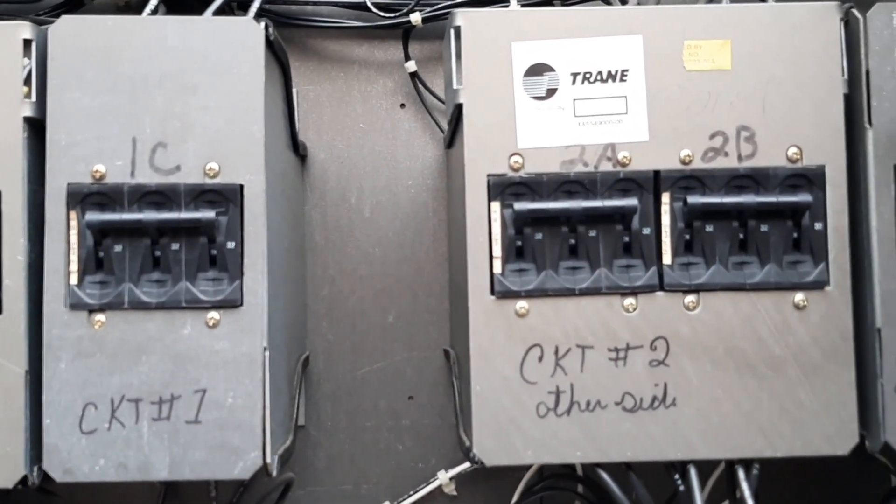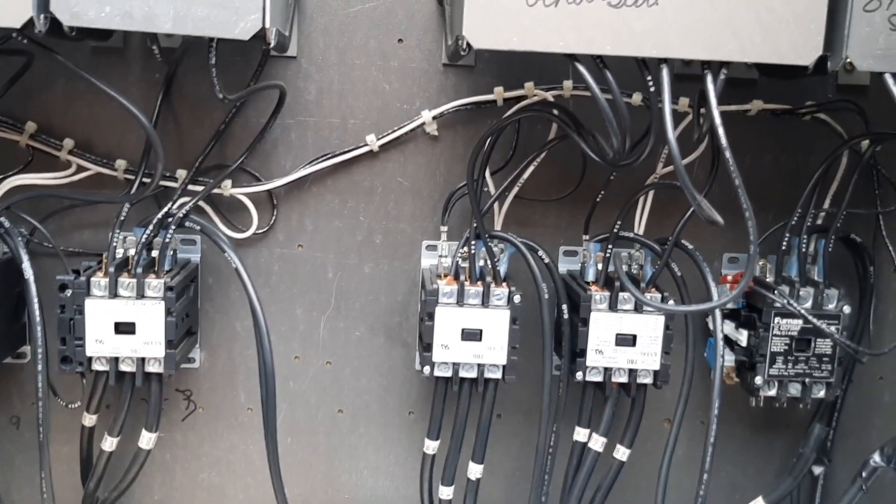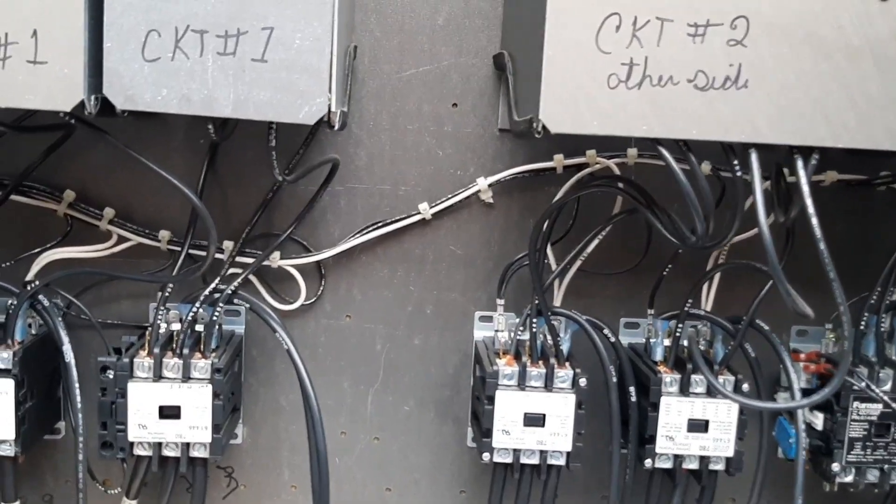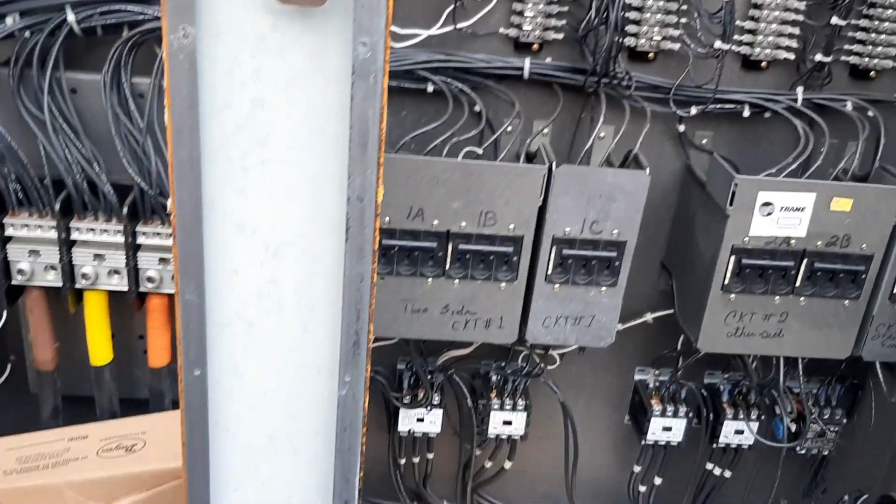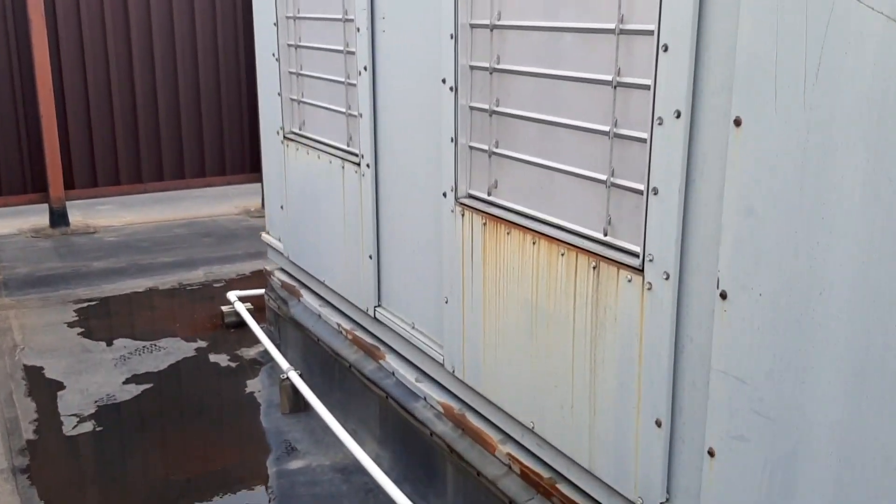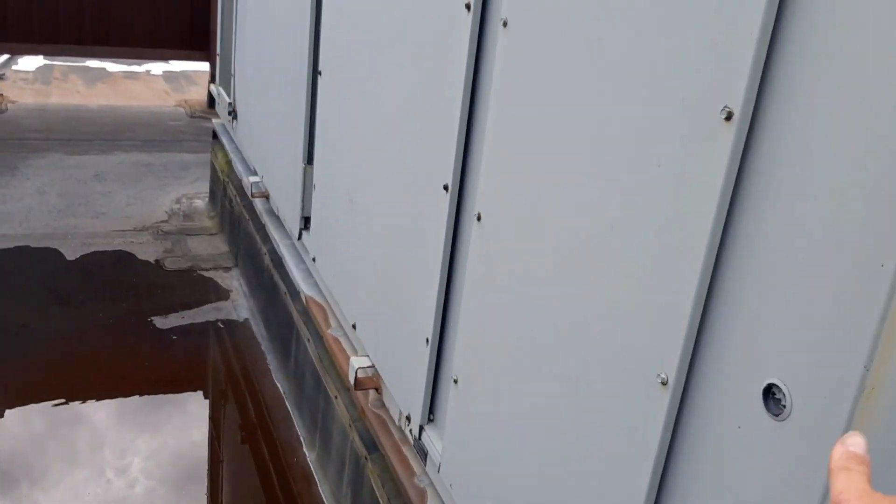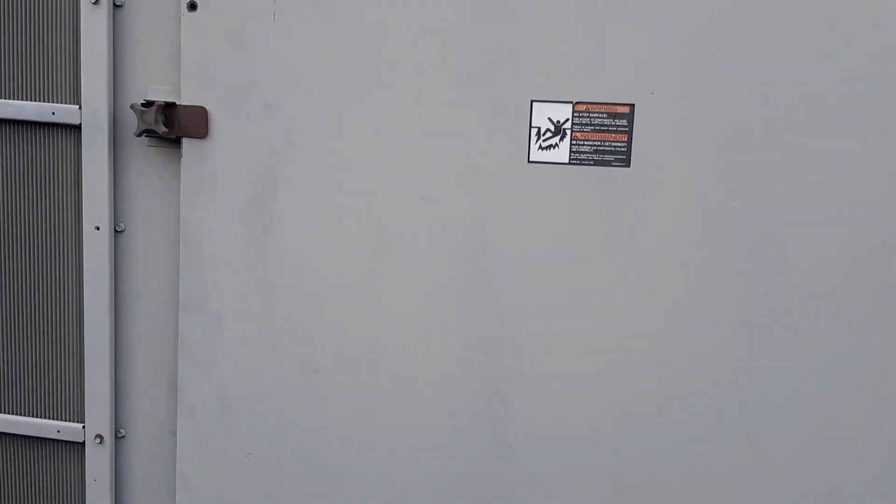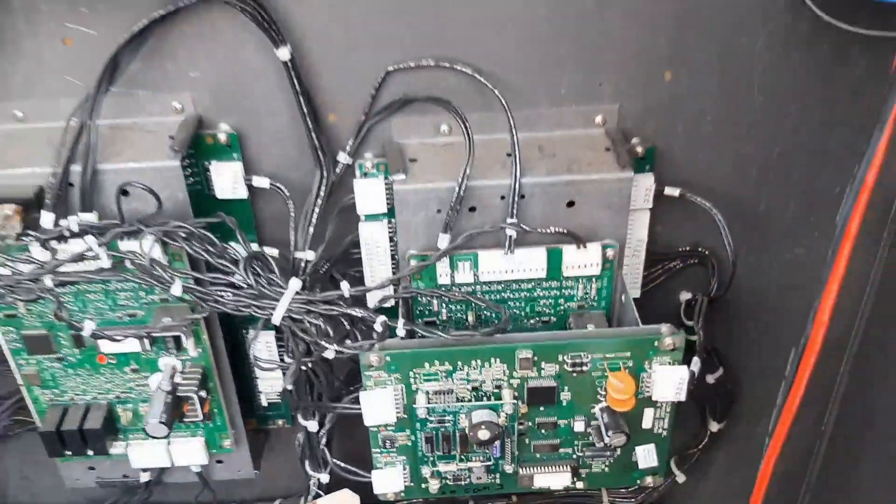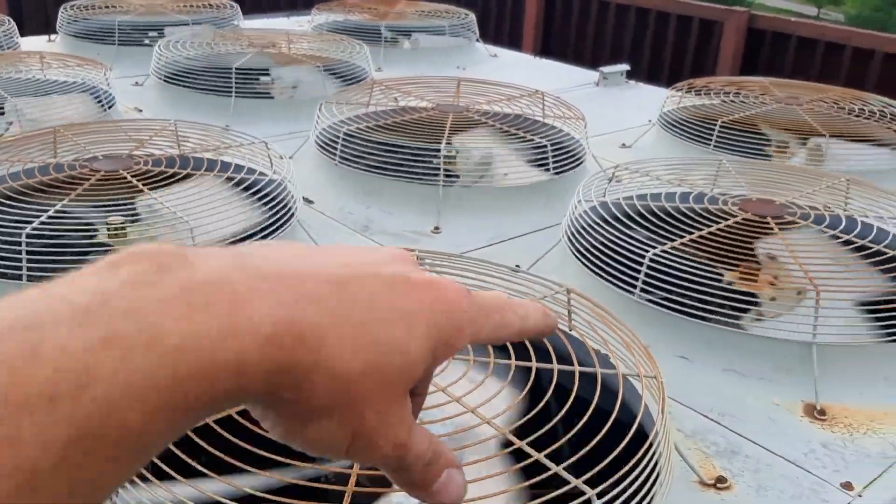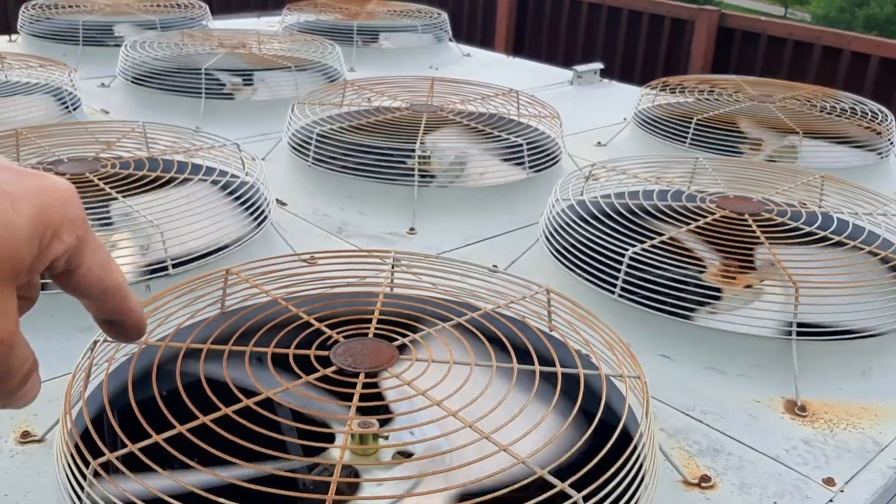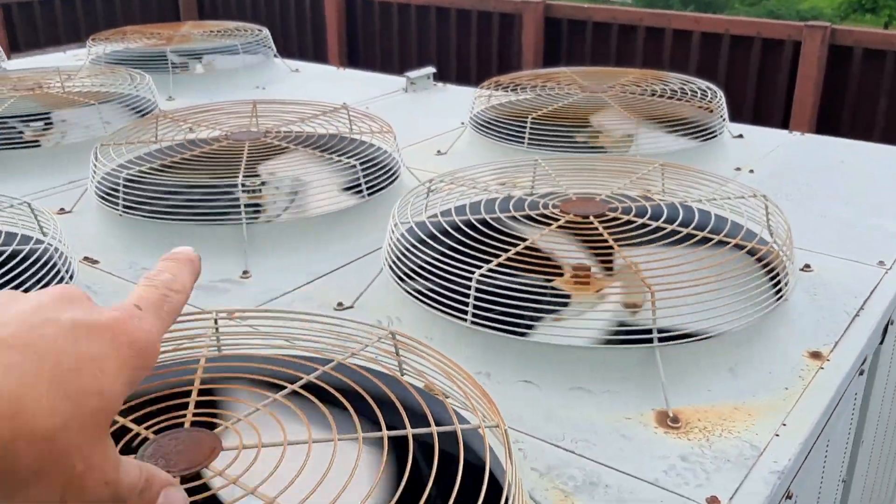I'm going to start with the condenser fan motors. Coils are clean, like I said, so we'll verify all my condenser fan motors running and then we'll move on down and plug into the system and see what's going on. Because I've got no noticeable issues. This is my exhaust out for the building pressure, and then all my VFDs are inside that panel there. All my fans on stage one at this side are running. I've got good heat coming out of my condenser.